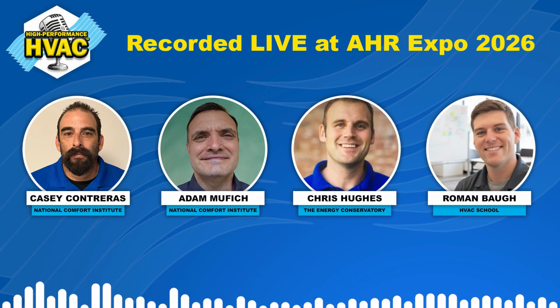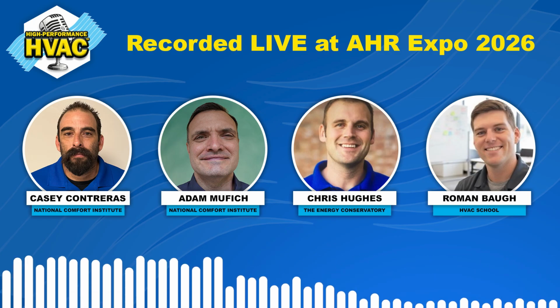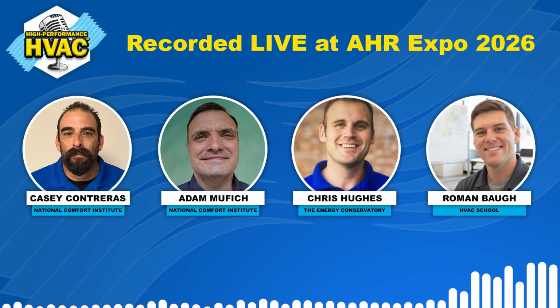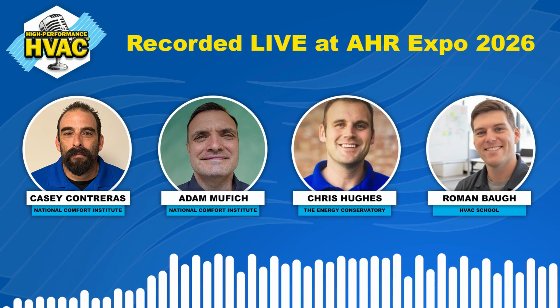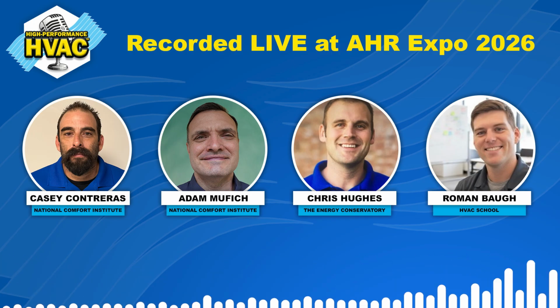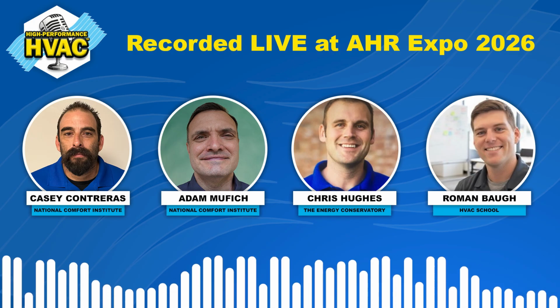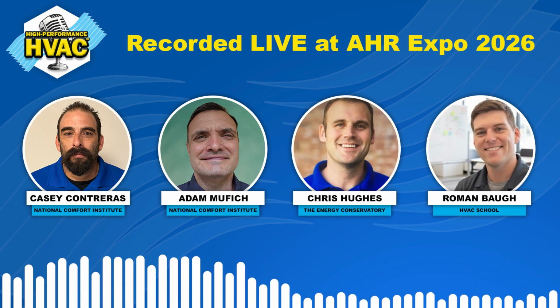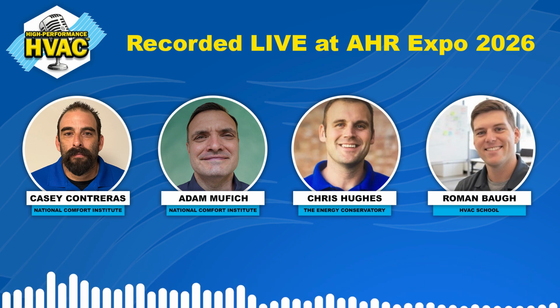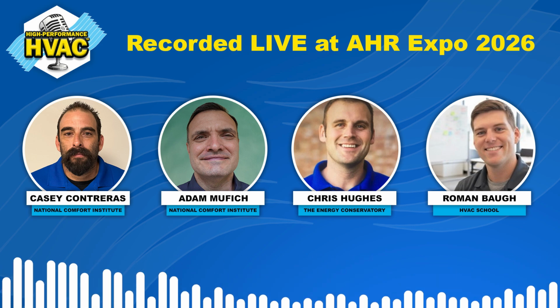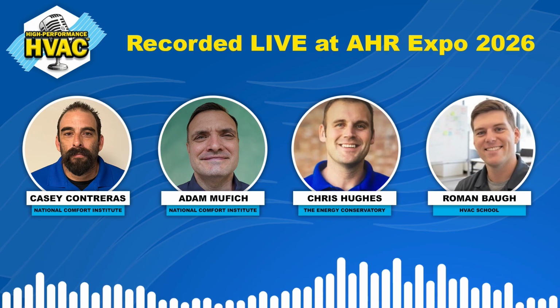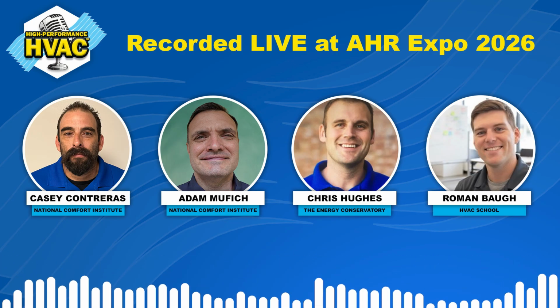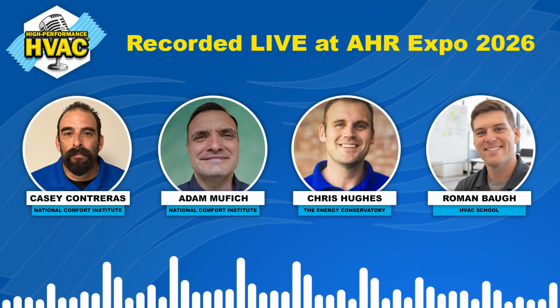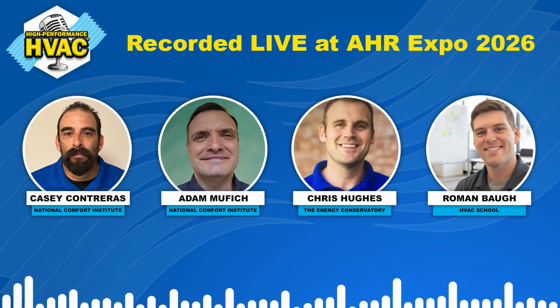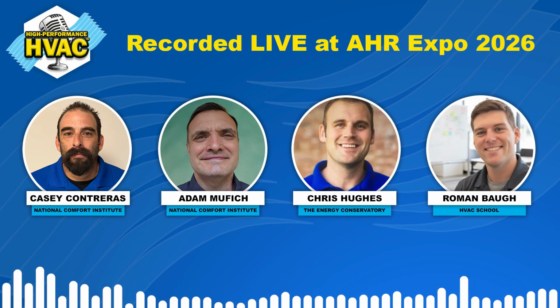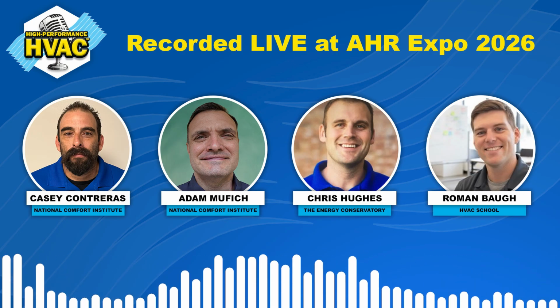Yeah. So it's funny. I saw a post that you made. I don't know if it was today or yesterday, but you forgot to turn your sprinkler off in Florida. It's Florida. We don't expect Florida weather to get down to like 20 degrees with like an 8-degree wind chill. And so, yes, I forgot to turn my sprinklers off, and it soaked my entire house. It soaked my tree. It soaked my heat pump, my AC unit, to the point where it actually blocked the lower housing airflow grill on the outdoor unit. And so it derated my capacity by a lot. Something you don't expect to have happen.